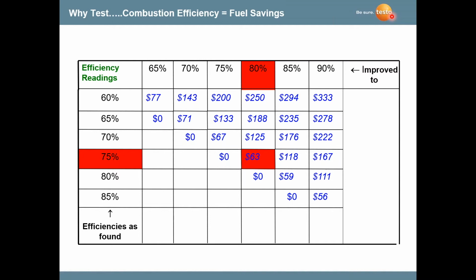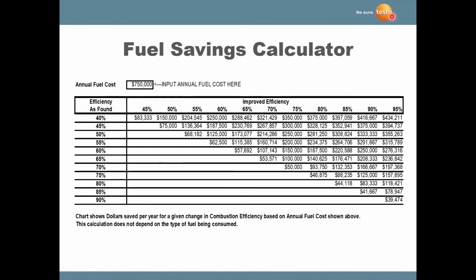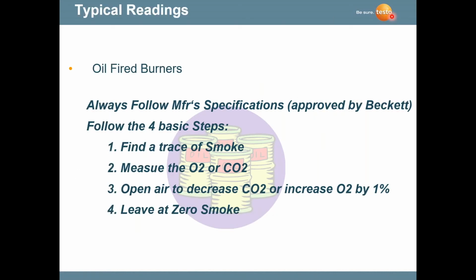Now, this doesn't apply very much for residential appliances, homes. But combustion efficiency matters where companies are spending huge amounts of money, Canadian dollars, US dollars, whatever it may be, on fuel cost. This is where you get into the big numbers, where hospitals, universities, industrial factories may be burning millions and millions of dollars of fuel a year. They want to make sure that not only do they have safe combustion, but also good combustion efficiency, because the fuel savings could be in the hundreds of thousands of dollars. And again, what we're measuring is oxygen and temperature. We know the fuel, and we can calculate the combustion efficiency. It's a calculation that we do.